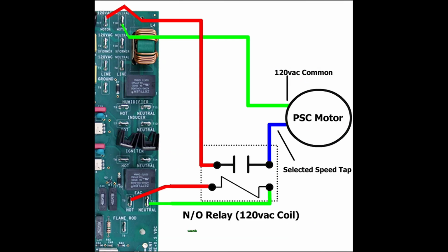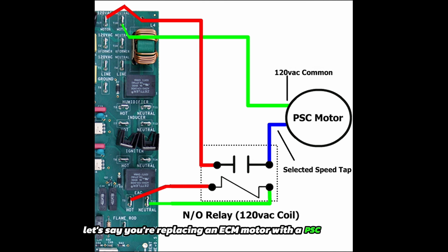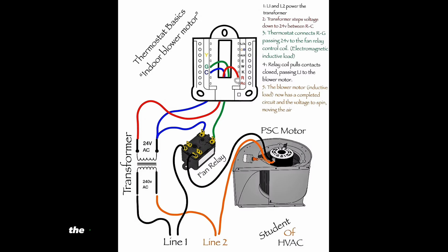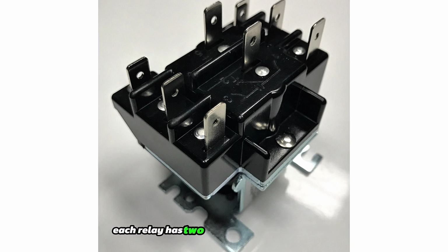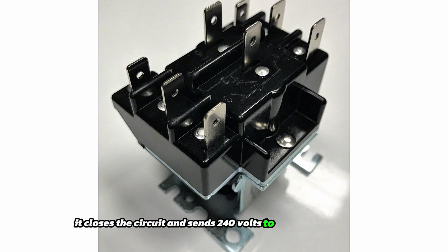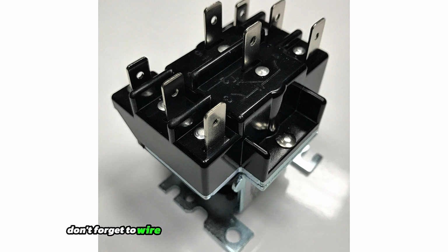Common relay wiring example: PSC motor. Let's say you're replacing an ECM motor with a PSC motor. You'll use two relays, one for cooling and one for heating. The G wire, blower call from thermostat, will energize relay number 1. The W wire, heat call, will energize relay number 2. Each relay has 2 terminals for the 24-volt coil, 2 terminals for the 240-volt line load. When energized, it closes the circuit and sends 240 volts to the correct motor speed. Don't forget to wire the run capacitor in parallel with the motor.